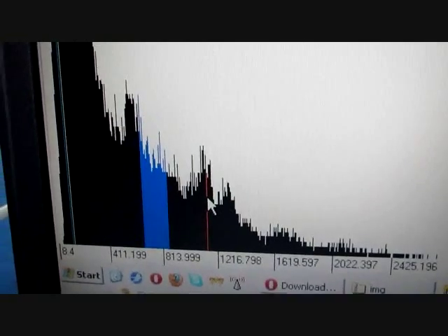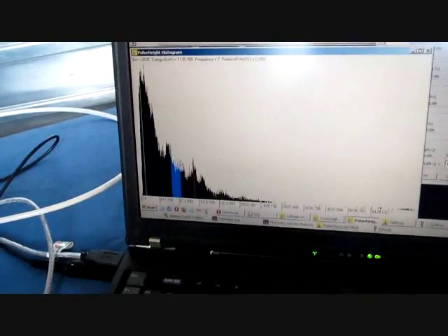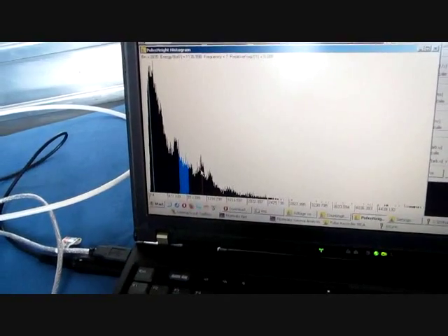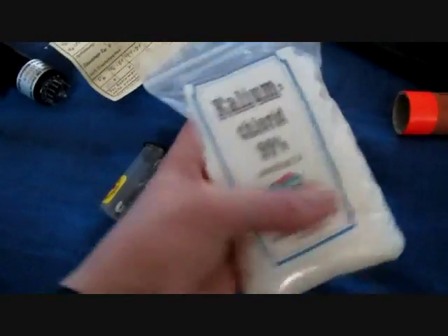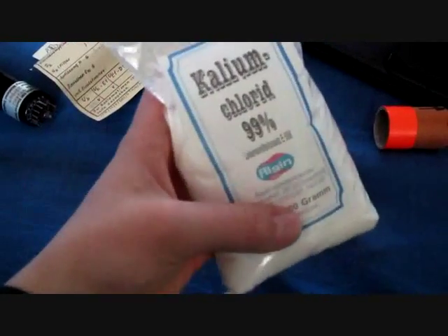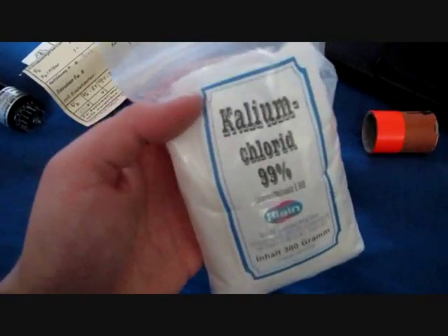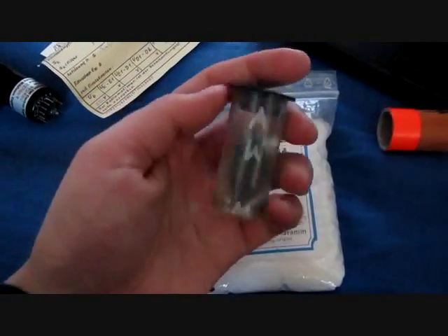So my energy calibration is a little off, as you can see, but it's still pretty good. You can still see how this works, how you can see the individual peaks. Cesium-137, cobalt-60 with the two lines here, and in the very front, right about here, there's actually also a peak from americium-241, but the detector is not entirely great at resolving such low gamma energies, but well, you can see it works. Let's try something else maybe. So we could try potassium chloride, for example, which has a nice peak at about 1400 keV.